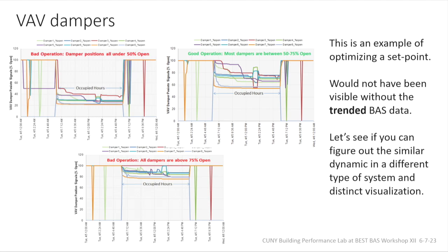There's kind of a tail chasing effect here that goes on. The fan slows down to the lower static pressure, and the boxes open back up. Boxes open back up, the pressure goes down a little further, and the dampers start to throttle, and so forth. So it's continuous action, but we're working the system at a lower pressure. Questions or comments? Robert, your comment is quite acute on this, and I think it speaks to the next slide. Well, actually, not to the next slide. We'll get to it in the slide after.